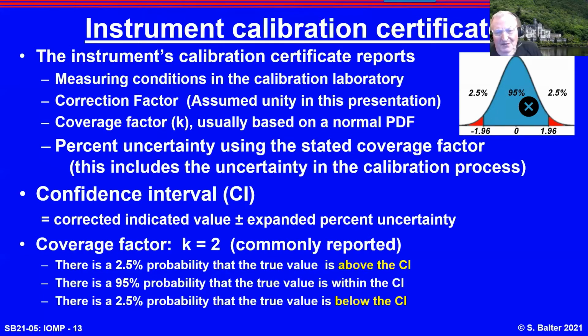There's a coverage factor, which is based on the normal PDF. And the uncertainty, that 3% I showed you, is based on a confidence interval using the expanded uncertainty. Roughly a K of 2 means plus or minus 2 standard deviations. So for the plus or minus 3% meter, or any accuracy, the chances are 2.5% that the true value is above that, and the chances are 2.5% that it's below that. I'm going to work an example in a minute to show you how this functions.